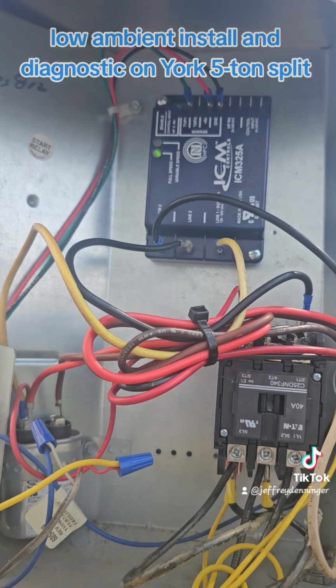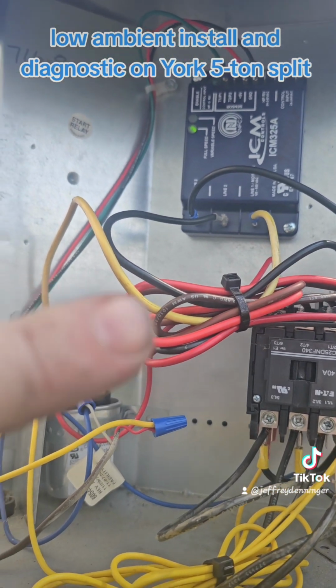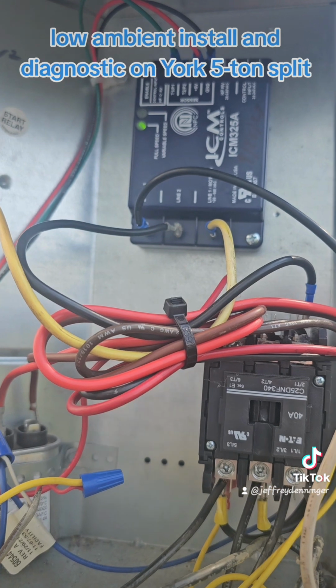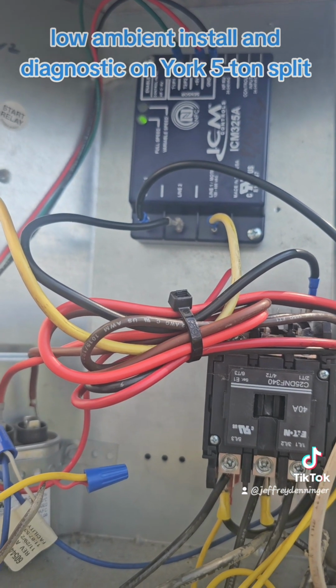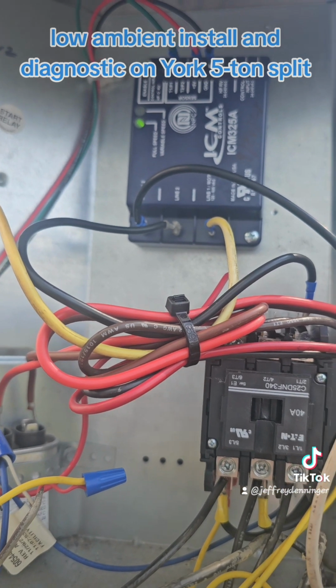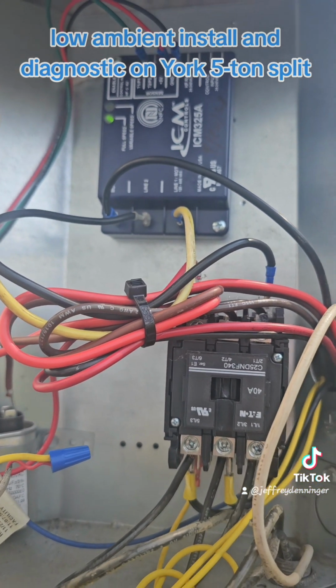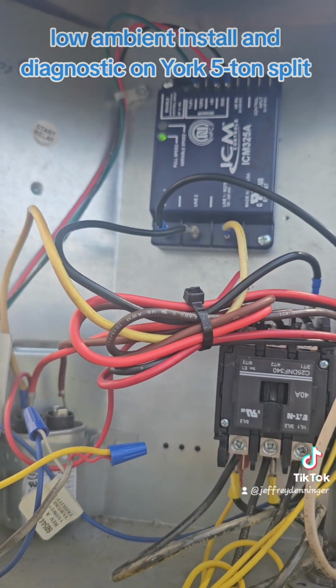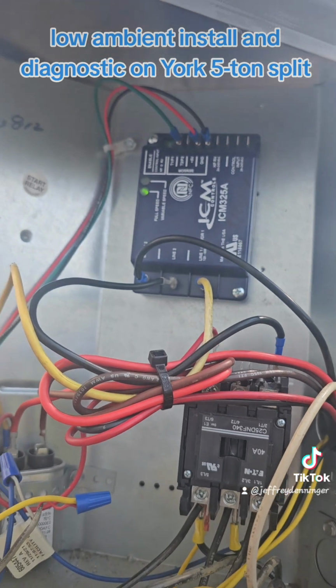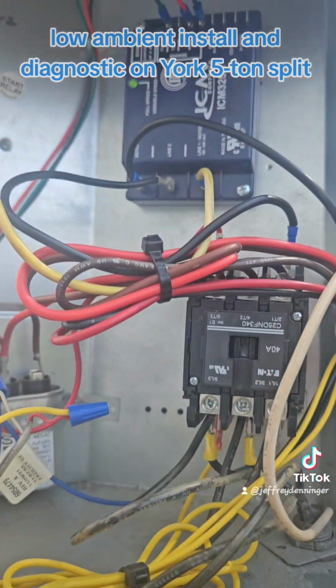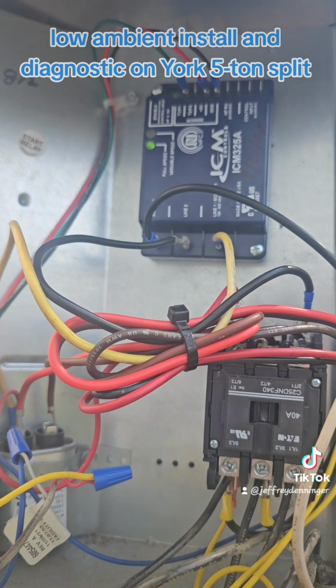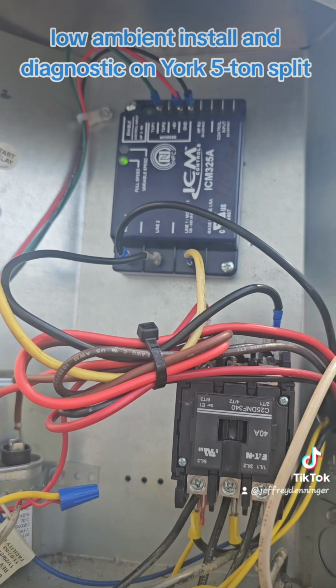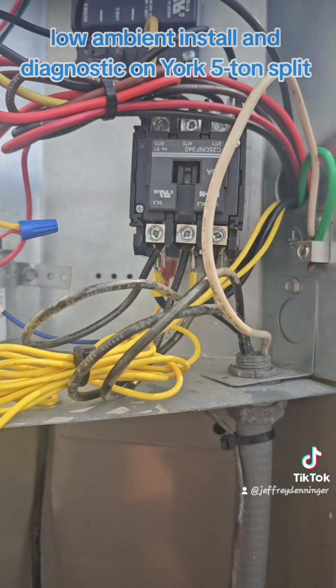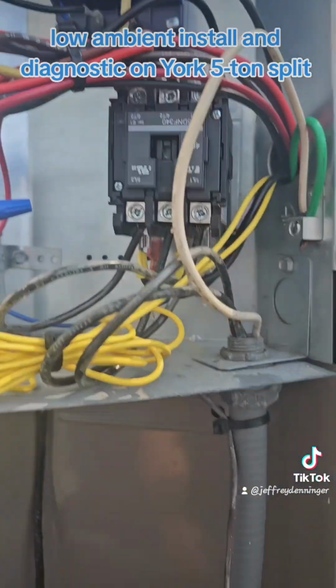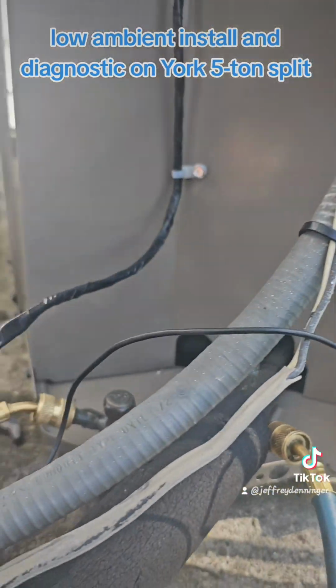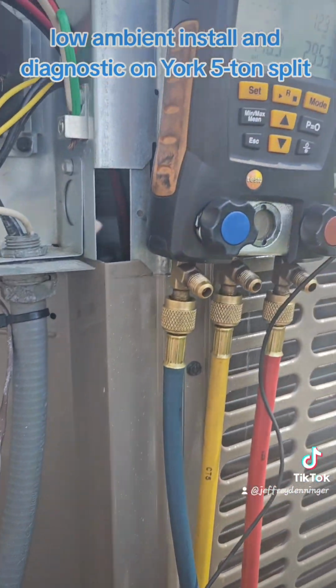We're now programmed. We have this controller set for 320 psi. No, sorry, 280 psi, which is about 90 degrees, to maintain full speed on the fan and good head pressure when it's cooler outside. I'll include the screenshots after this of the app. Very simple to use, very handy. All the wires all neatly tied up. And we are up and running.